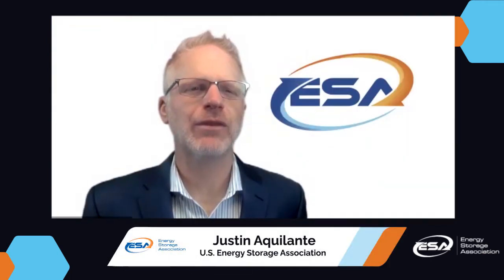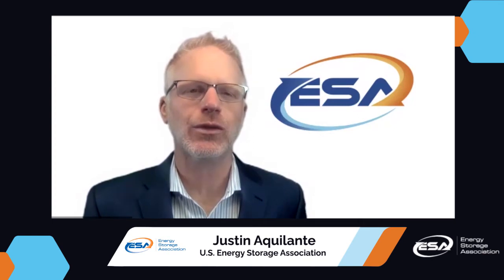Seth, there are two types of electrical grounding that are currently being used in battery energy storage systems, ungrounded and grounded. Can you explain these two systems? Yes, absolutely. And it's very important to understand the difference between these two systems because the safety that goes along with it will be dictated by what system type the battery energy storage system is operating on. So the grounded system, again, we are very familiar with this in the United States. This is what is in our household, a solidly grounded system. You have a hot, a neutral, and a ground in any standard outlet.